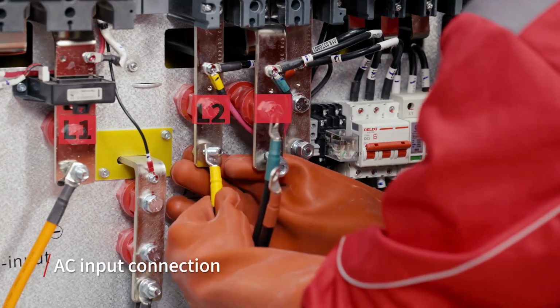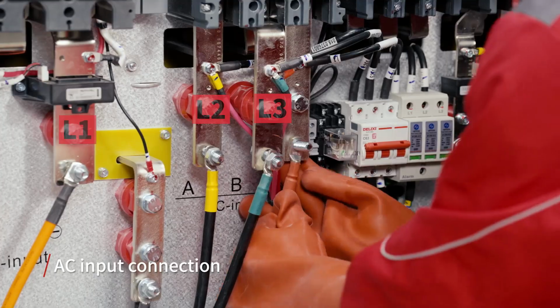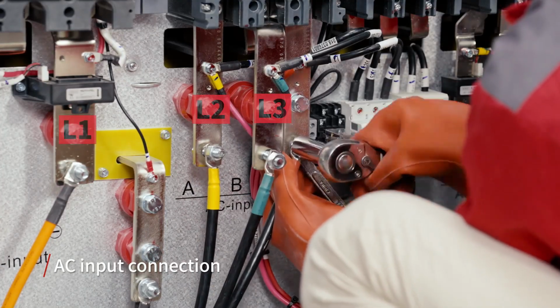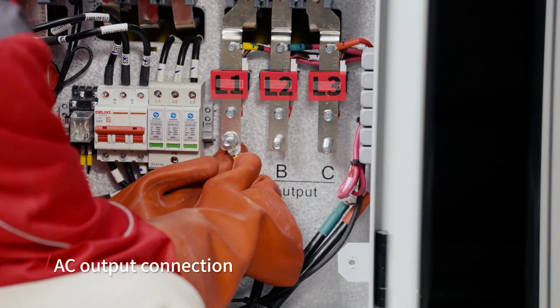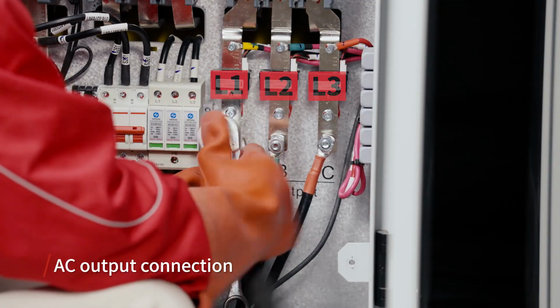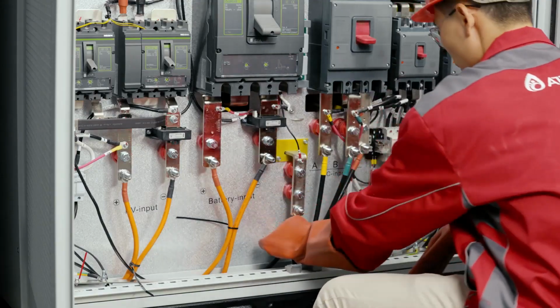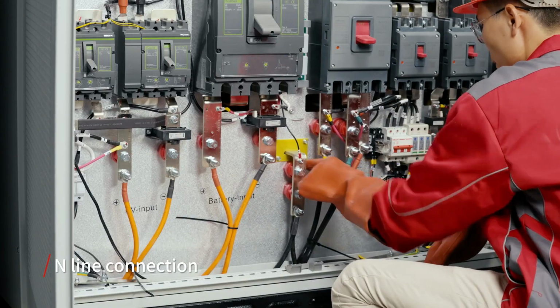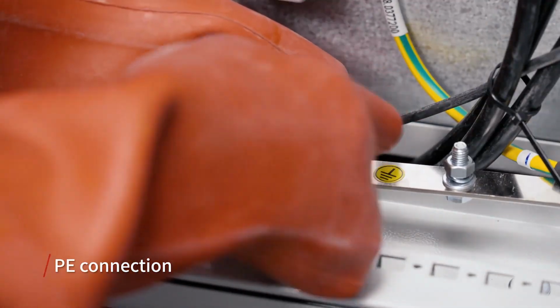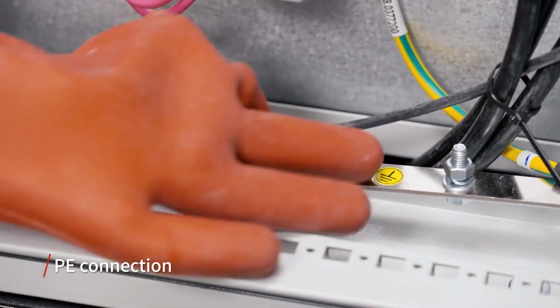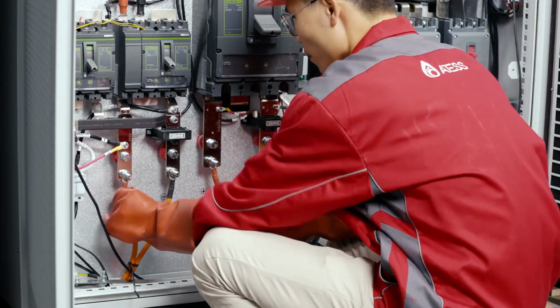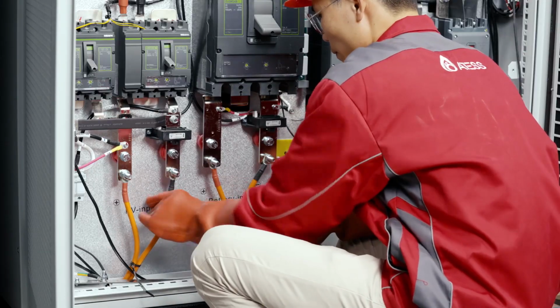Connect grid cables to the breaker marked AC input. Pay attention to the phase sequence. Connect load cables to the breaker marked AC output. Also pay attention to the phase sequence. Connect the N cables of grid and load to the N bar of HPS. Connect the PE cables of grid and load to the PE bar of HPS. Check whether the cables are connected properly and securely.